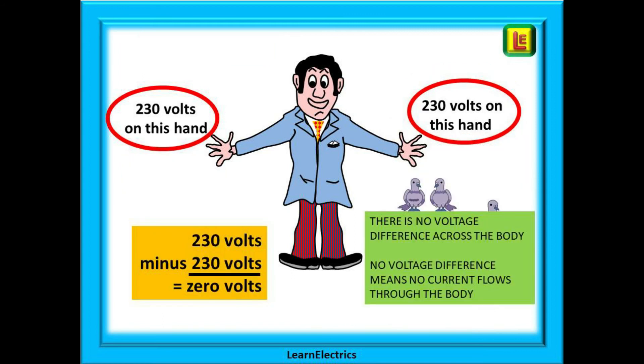Just to reiterate: 230 volts appears on each hand during the fault because Eric was touching the water pipes and the socket casing when the fault occurred. 230 minus 230 equals zero volts, so there is no voltage difference across Eric's body. No voltage difference means no current — Eric is safe. Fractions of a second later the fuse blows and everything becomes zero volts, a condition of safety.